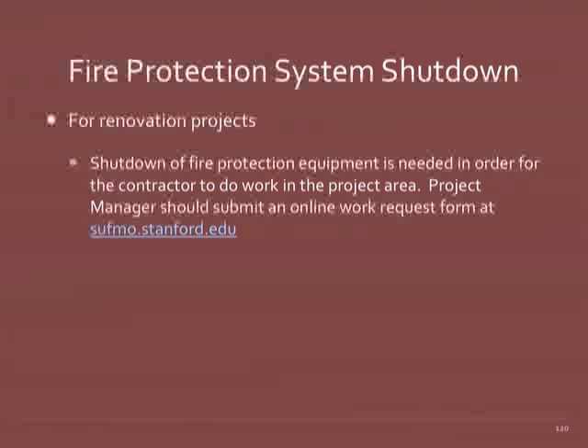On renovation projects, as well as the hazardous material summary report we provide, we have to coordinate the shutdowns of fire alarm or fire sprinkler systems. Almost every one of your renovation projects will have that to one degree or another. Most of our major buildings are sprinklered. If you're taking a wall down, it can affect a sprinkler system, and if you're putting one up, it does the same thing. It can also affect an extinguisher location or an alarm device. So it's critical we get involved, because we have to make sure the remaining occupants of the building have a fully functional sprinkler system, alarm system, and extinguishers. The shutdown is basically done through our technicians, the physical shutdown of devices. They're a charge-out group, and again, our website has the work request form for that.